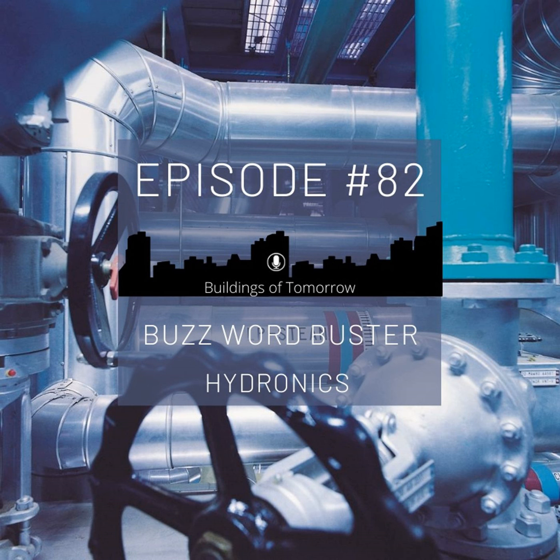And these, as I said, are standard approaches that you can normally also select on an electronically controlled pump as a strategy. Now, the next two that I would like to talk about are most often implemented or are in need of a building automation system. And the first one is that we say, let's have delta P constant somewhere at the end point of the plant, meaning across the consumer and the control valve.